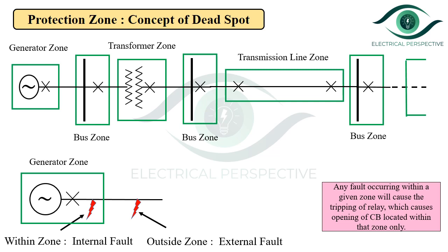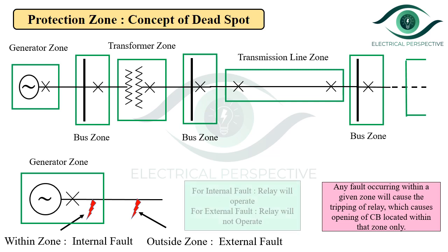The significance of the protection zone is that if the fault occurs within the zone, then only the relay will trip and the circuit breaker will operate. This means the protection system will respond only for the internal fault. In short, for an internal fault the relay will operate; for an external fault, the relay will not operate.